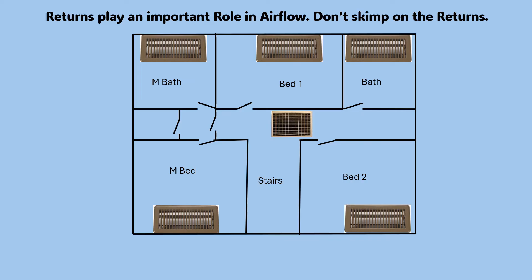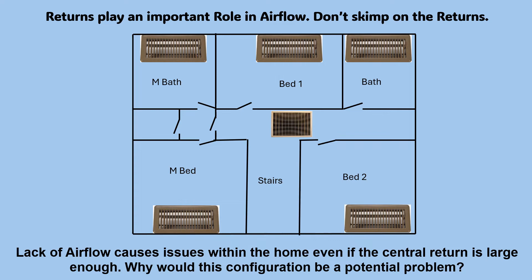No contractor goes through a residence and says they're not going to put a supply in a room, but many try to limit the amount of returns, as you see in this example. Lack of airflow causes issues within the home even if the central return is large enough. This causes a problem because the doors in each one of these rooms without a return act as dampers. When the doors are open, the air can make it back to the return. When they are closed, the air can't make it back to the return, and the central return is not getting the return air from that room, lowering airflow.